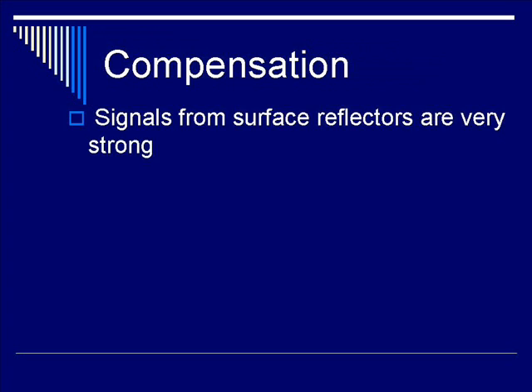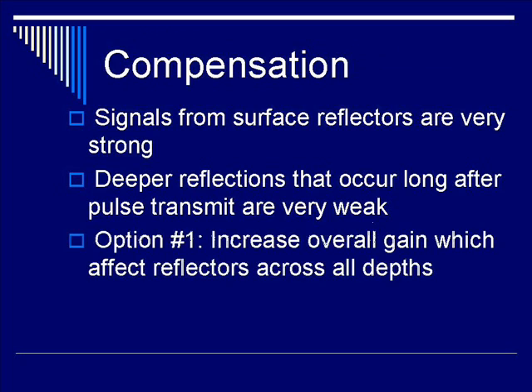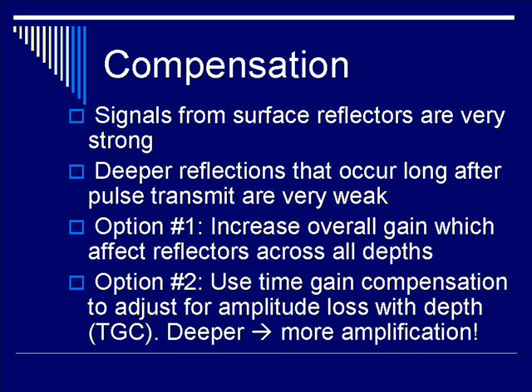Let's discuss compensation and how it's used. Signals from surface reflectors are very strong. On the other hand, deeper reflections that occur long after the pulse is transmitted are very weak. To balance things out, you have two options. The first option is to increase the overall gain, which unfortunately affects reflectors across all depths — so you have no balancing. However, you can opt for option two: time gain compensation, which adjusts for the increased amplitude loss with depth. Therefore, deeper reflectors get more amplification, whereas shallower reflectors get less.